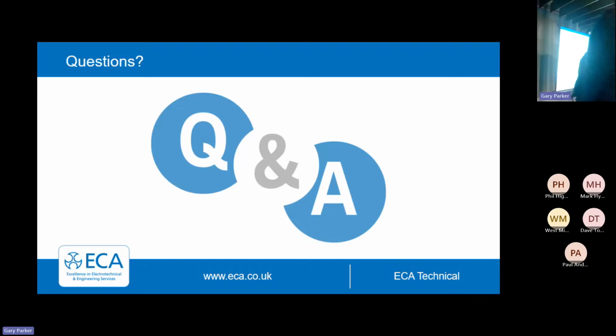It's a good point, and this was something that could have easily been in the corrigendum - it was probably picked up a little too late. The concept's great though. If you take out things like PV and just think of a normal diesel generator, if you have that as an additional supply to a building and there's a fault somewhere, the fault is going to be seen not when you're on mains, not when you're on gen, but when both are happening. When you've got that plus that, it equals a bit more than that - that's when the fault's going to happen. So for those systems, yes, I can understand why you need switchgear that's effectively double rated. It's got to be able to work with the highest, and what probably isn't considered well, the lowest fault. It's fine when you've got that set up, but if you go from mains to diesel genny, the fault currents drop massively and half the circuit breakers won't work. That one was effectively an anomaly, and I'm fairly sure that's been picked up and will be changed. I don't think that's the intention, but you're absolutely right.